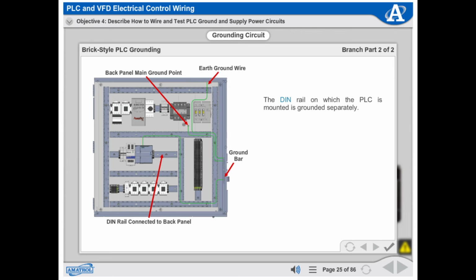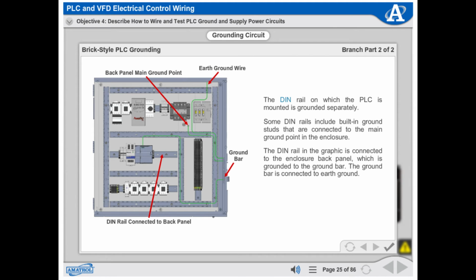The DIN rail on which the PLC is mounted is grounded separately. Some DIN rails include built-in ground studs that are connected to the main ground point in the enclosure. The DIN rail in the graphic is connected to the enclosure back panel, which is grounded to the ground bar. The ground bar is connected to earth ground.